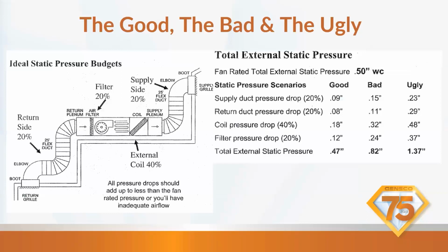But again, here's the good, bad, and ugly. This is just so you can visualize static pressures. Also, this is a great slide because our good static pressure, our supply duct, here's our return, here's our supply. If we took our supply reading, it should be about 0.09 on a good. Our return air, we should be about 0.08. This one is a coil pressure drops 0.18. Filter pressure drop is a 0.12. All that total, it's just 0.47. So realistically, we want a 0.47 across the blower motor and the coil.